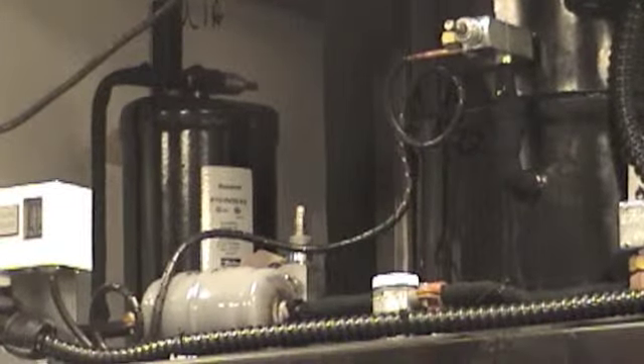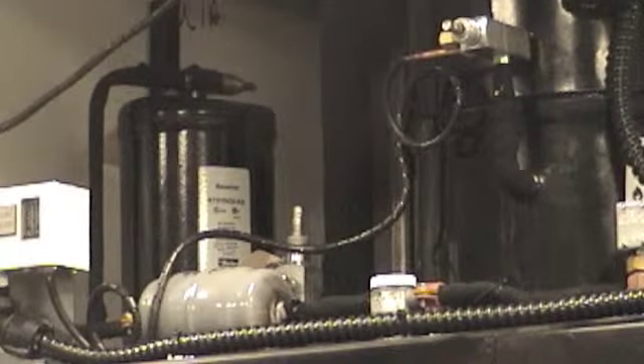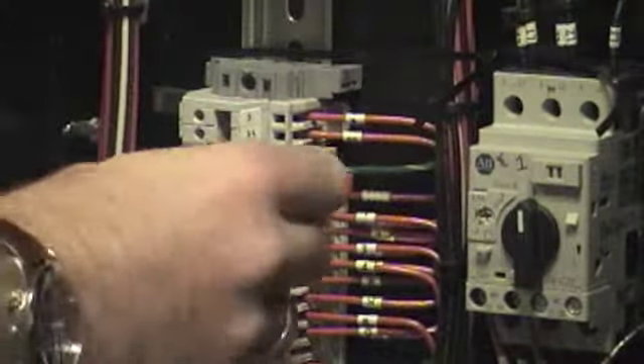So once we're done opening all 3 valves, backseating every valve, we're going to head back to the electrical box to put the refrigeration fuse in the trap. So now that we've opened up all of our service valves, we'll take out one of the 2 fuses that we supply for the refrigeration system. We'll put it into the front of the trap there. Close it. And now your refrigeration system's ready to run.